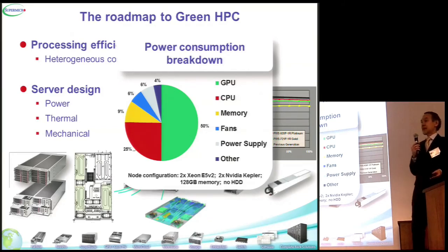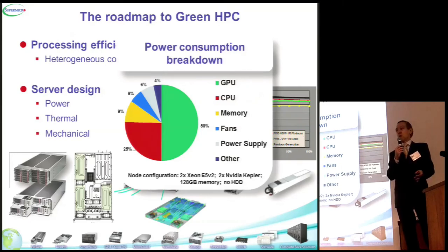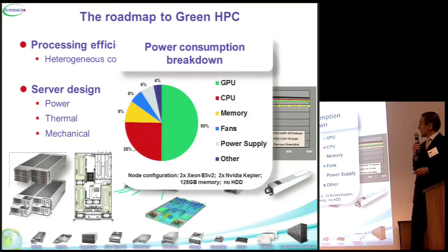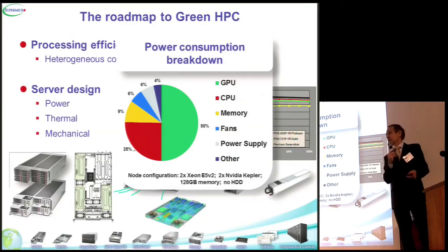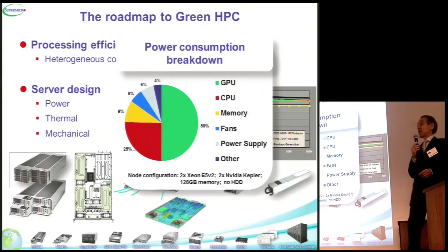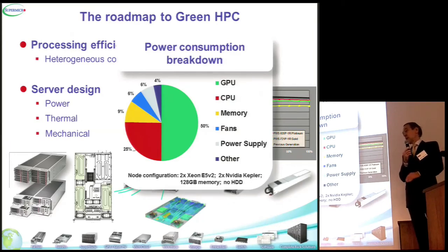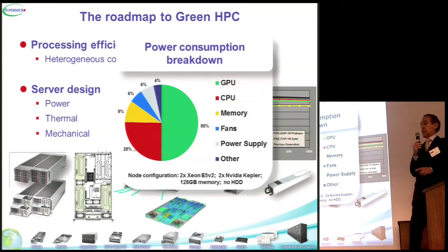You can see that 50%, as probably would be expected, is for the GPUs, 25% CPUs. But you can see that the fans and the power supply combined take 12% of all the power, so that's perhaps not an obvious thing. Just a remark: this is with a synthetic load that tries to load the GPUs and all the CPU cores maximum. In a real system, it will depend on how well the applications are optimized, whether they run more on the CPU or the GPU cores. It probably will be very difficult to have full load on the GPUs and the CPUs at the same time. Here you have that because it's an artificial synthetic load.